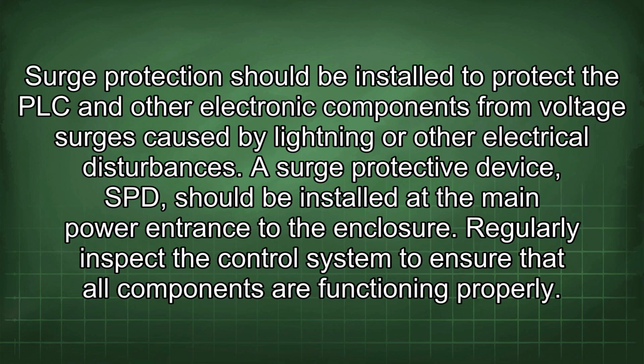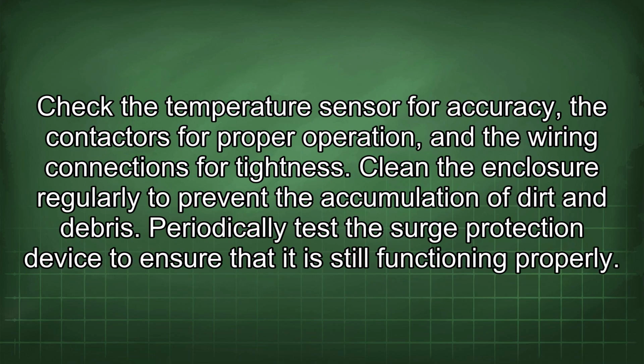Surge protection should be installed to protect the PLC and other electronic components from voltage surges caused by lightning or other electrical disturbances. A surge protective device, SPD, should be installed at the main power entrance to the enclosure. Regularly inspect the control system to ensure that all components are functioning properly. Check the temperature sensor for accuracy, the contactors for proper operation, and the wiring connections for tightness. Clean the enclosure regularly to prevent the accumulation of dirt and debris. Periodically test the surge protection device to ensure that it is still functioning properly.